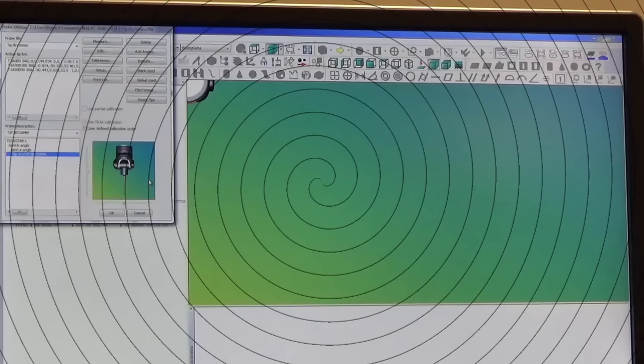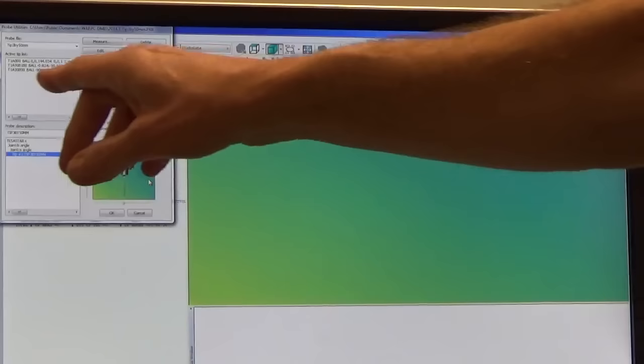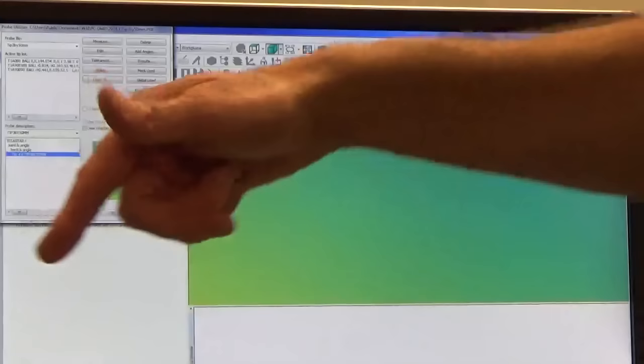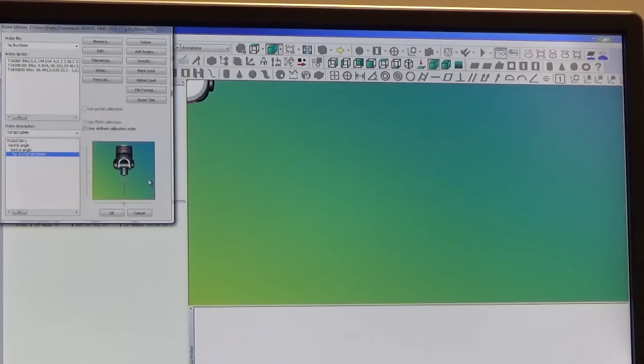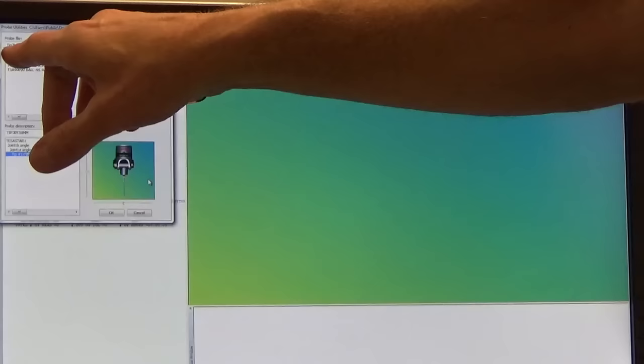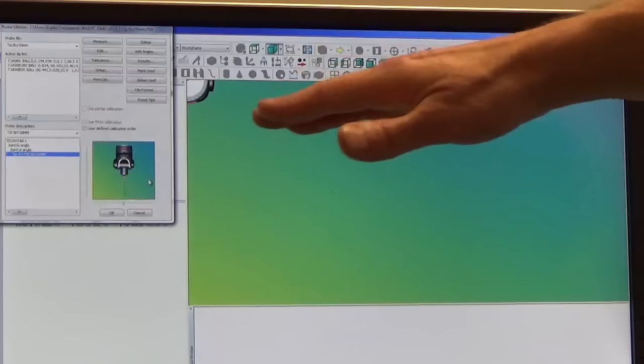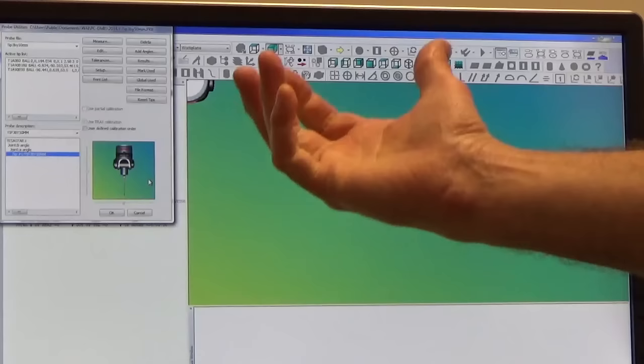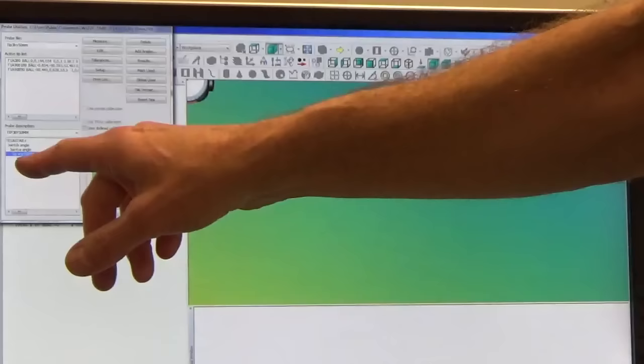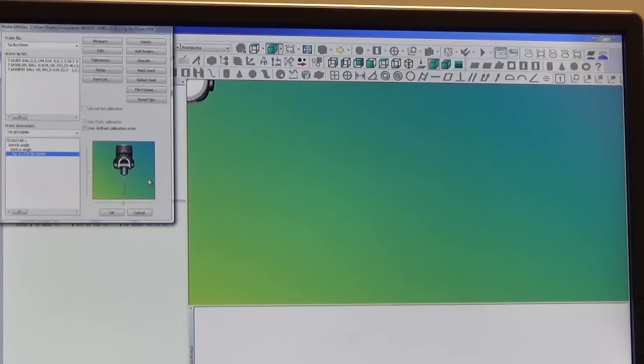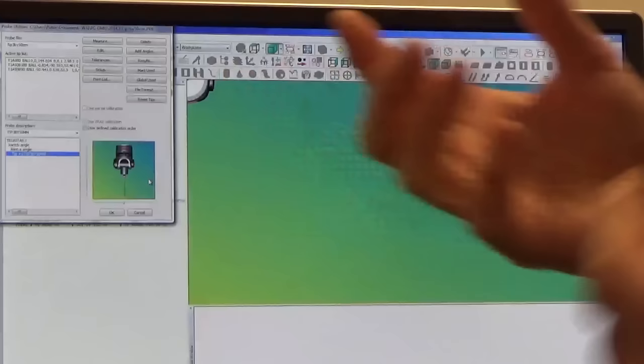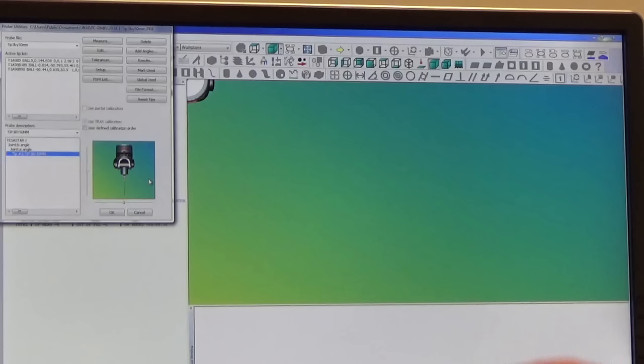So I have redone the calibration and this time we came back with no errors. And the way we know there are no errors, there's no asterisk in front of these line items here. If there was an asterisk in front of any one of them it would mean that particular item failed. So we have a complete calibration. The issue that we had was in my specification of this probe tip. I had not used this probe tip before and I incorrectly had said this was a four millimeter ball, it is in fact a three millimeter ball. So given that all of the calibrations failed, that's a good indication that you have a setup issue.